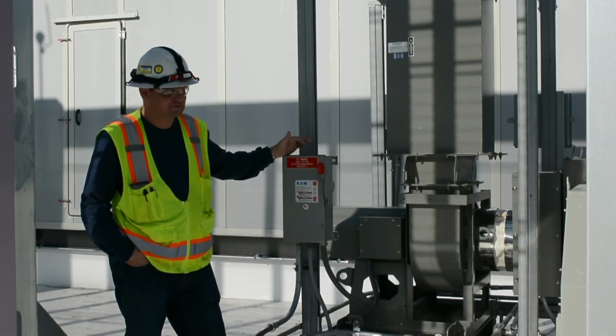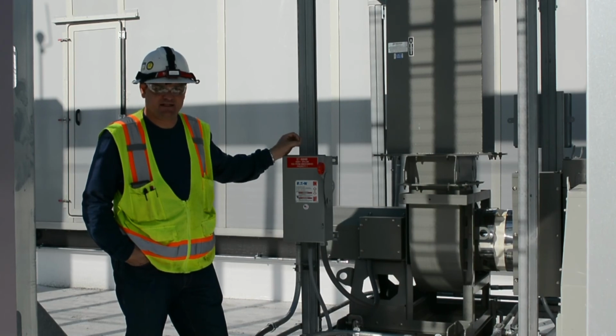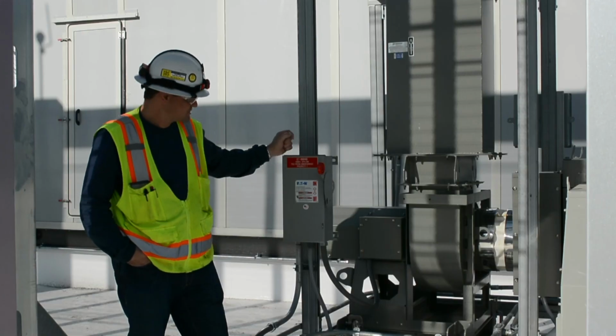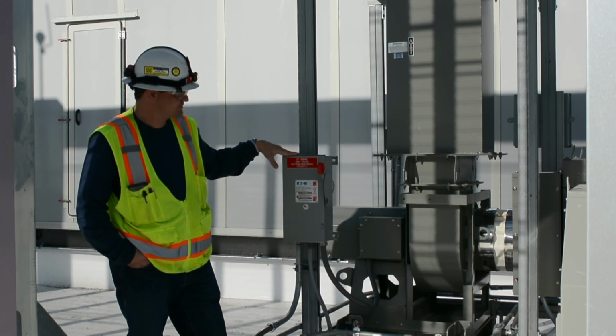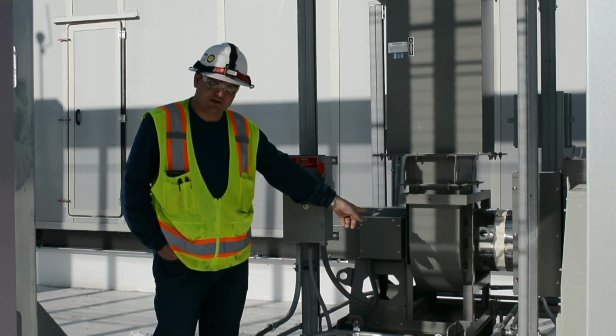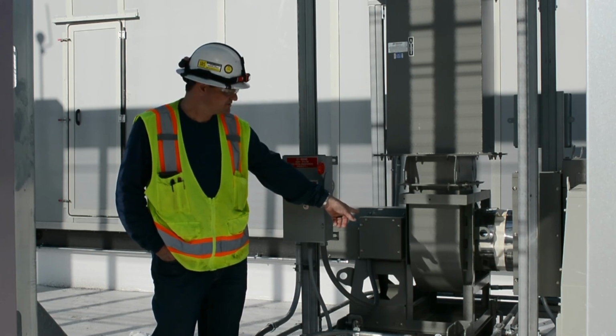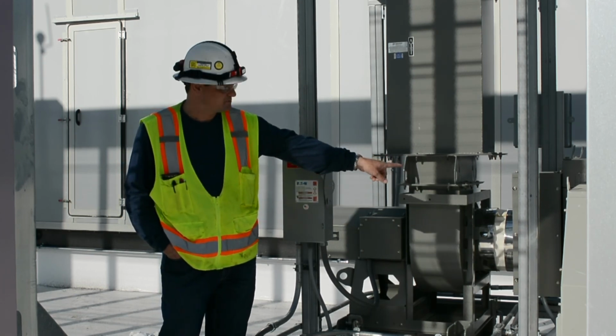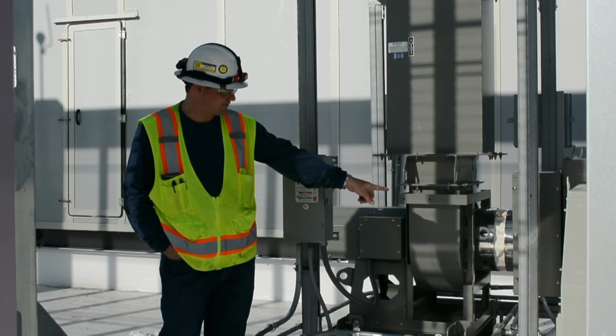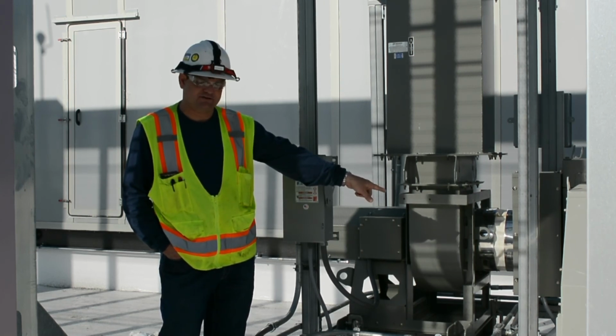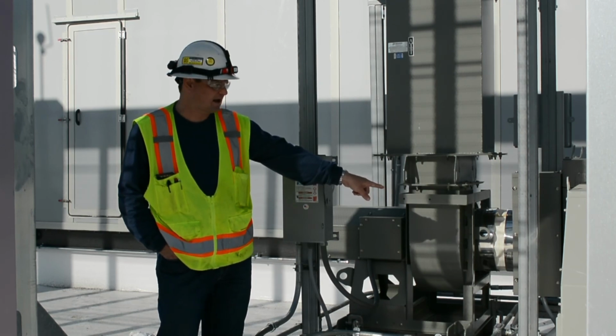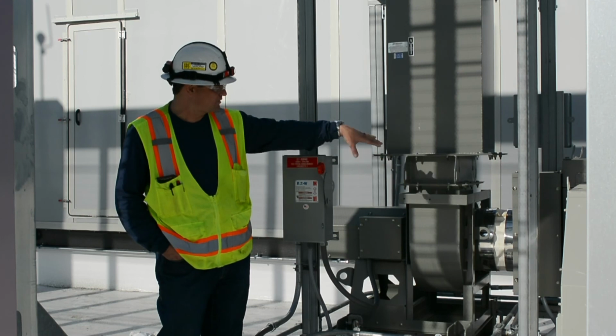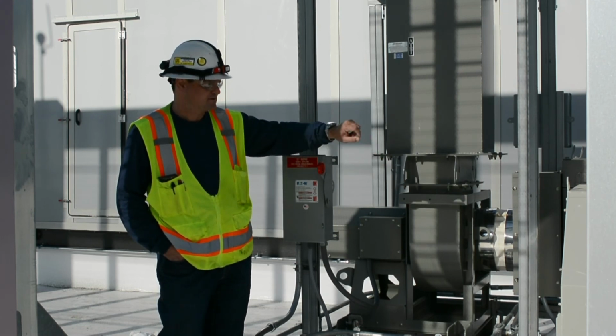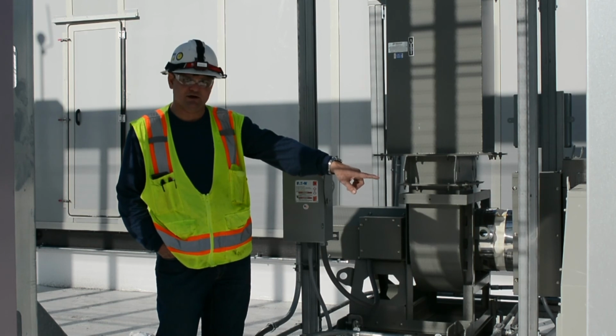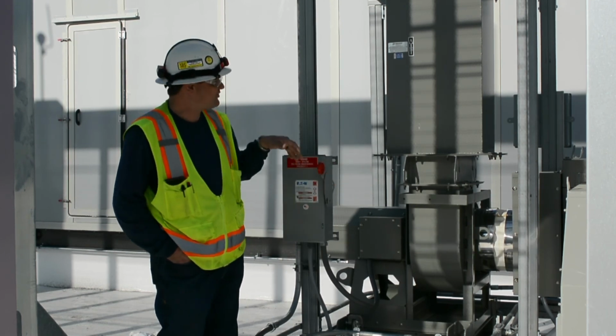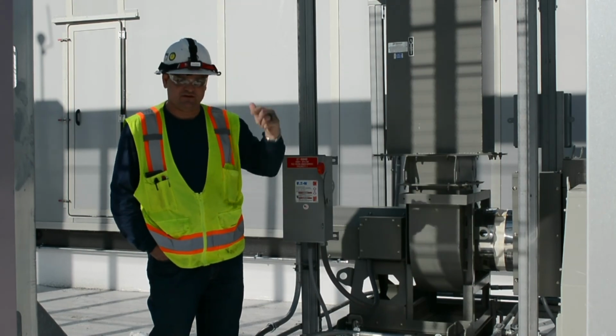These are the high plume Vektor fans for the biosafety level 3 laboratory on the 4th floor. Your unit-mounted disconnect is here. This is a utility set fan, direct drive, no belts, and it's connected to a common plenum with backdraft damper, and that's a motorized damper. The damper gets opened by the control system to enable the fan. Once the damper is proven open, the variable frequency drive will modulate this fan to maintain a duct pressure. There's also a dilution air damper located here that is going to mix fresh air with the exhaust air to dilute it before it's exhausted to the atmosphere.